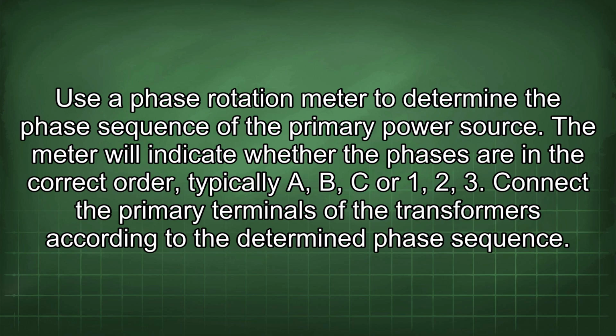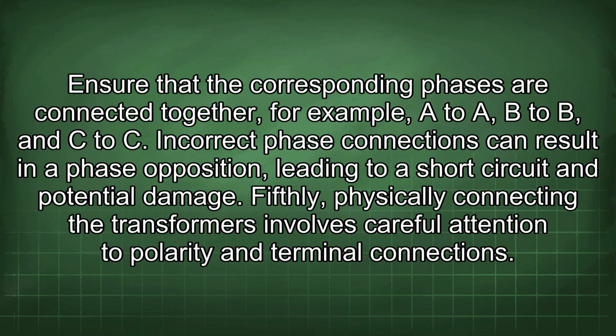Connect the primary terminals of the transformers according to the determined phase sequence. Ensure that the corresponding phases are connected together, for example A to A, B to B, and C to C. Incorrect phase connections can result in a phase opposition, leading to a short circuit and potential damage.